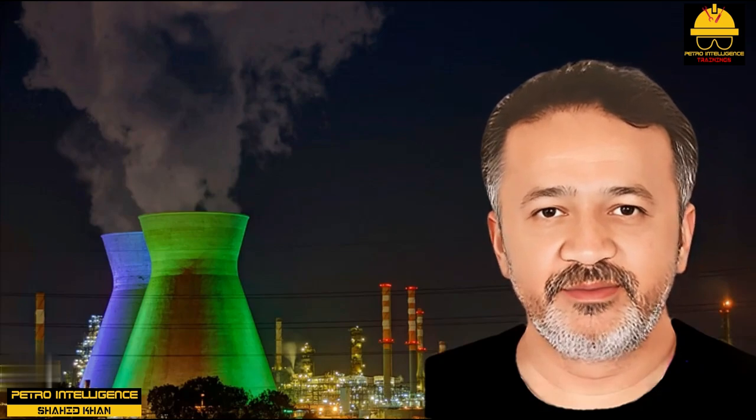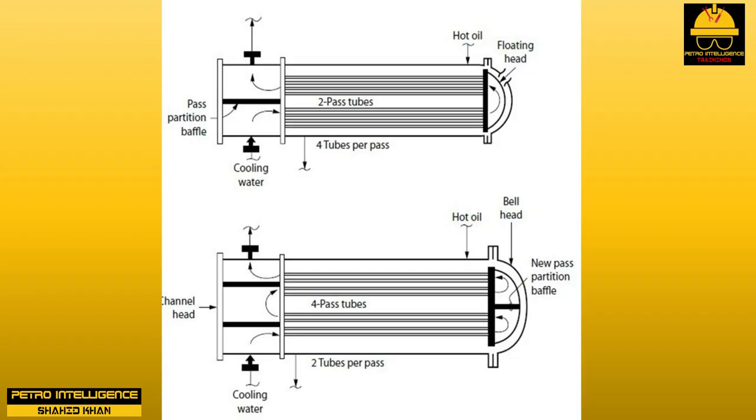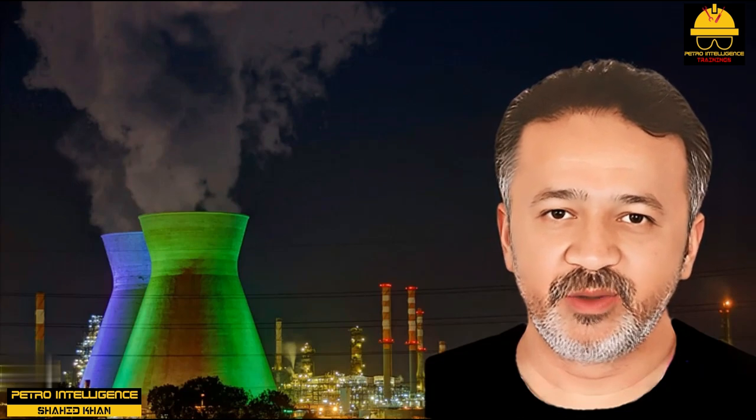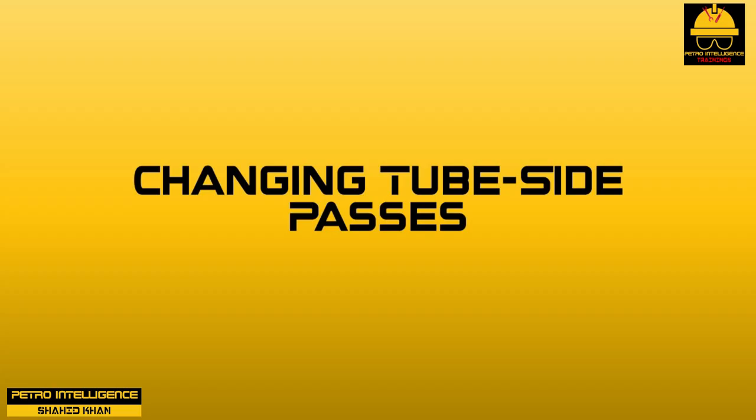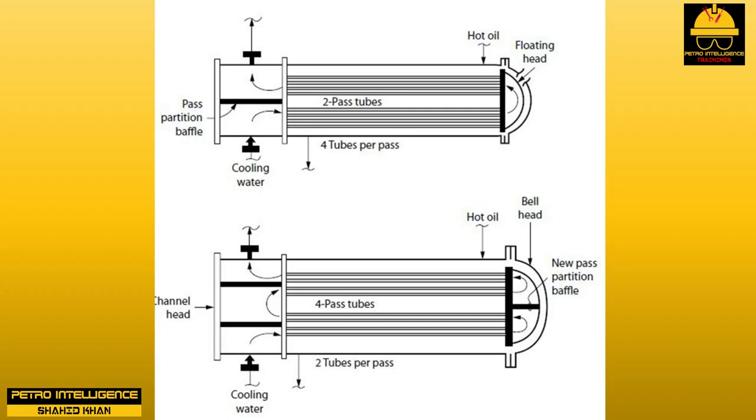One mistake I have made in the past is due to air accumulation in the channel head — I confused the effect of trapped air with fouling. Especially on startup, air may be trapped both above and below the pass partition baffles. The air can fill some of the tubes, especially at lower tube velocities, and effectively reduce the exchanger surface area. Opening the vents on the channel head to vent out accumulated air is a good method to restore lost cooling capacity. Initially I had confused this lost cooling capacity with fouling.